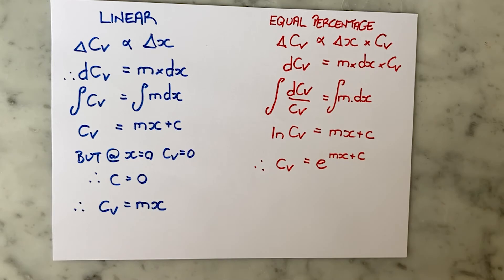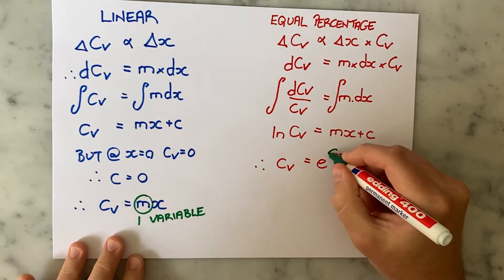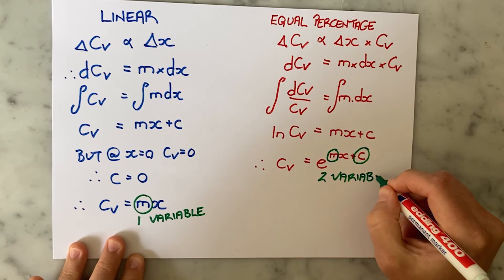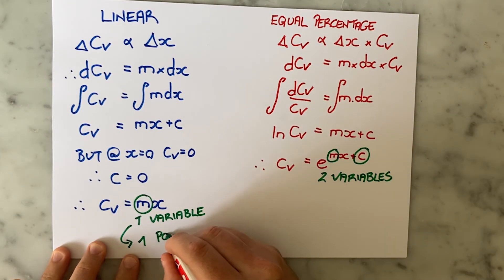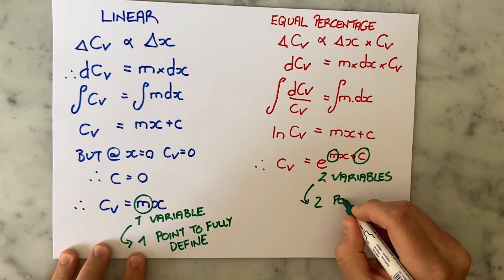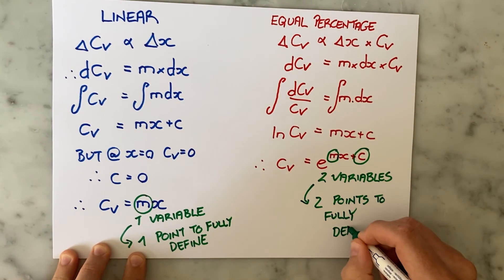So I have two variables that I need to solve for, which also means that I need to know or define two points—meaning two pairs of valve opening and CV—before I can fully characterize an equal percentage valve.